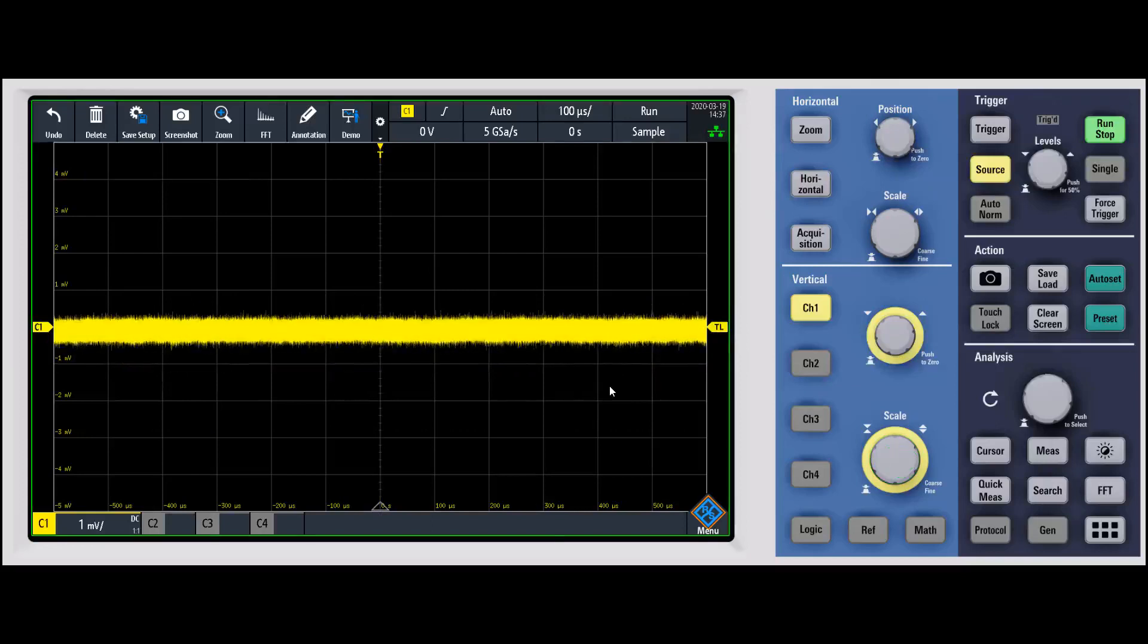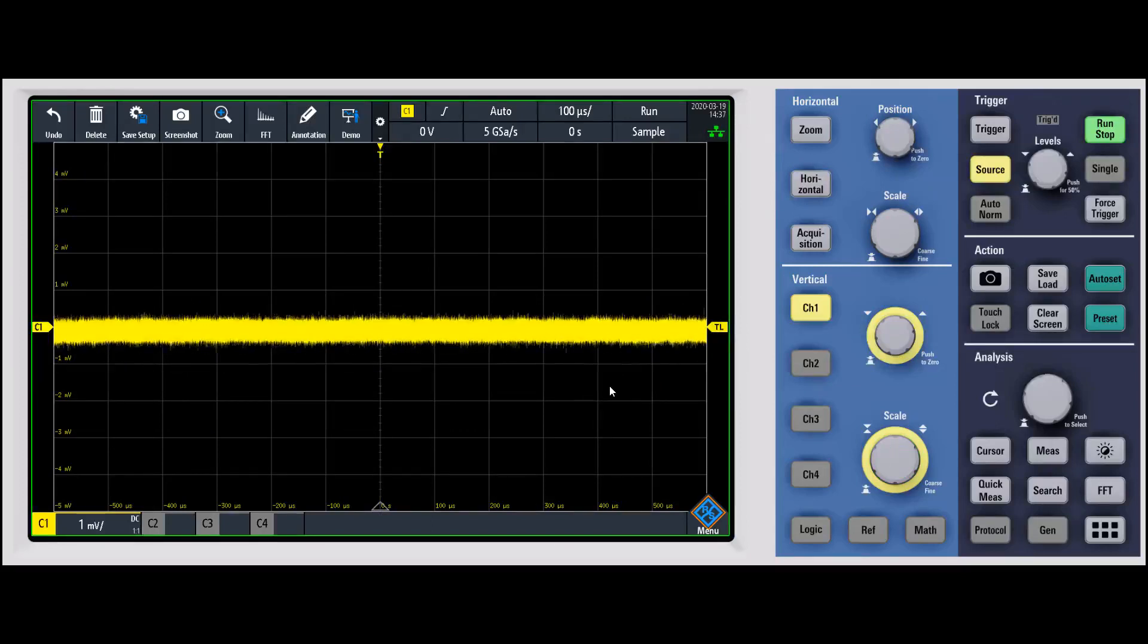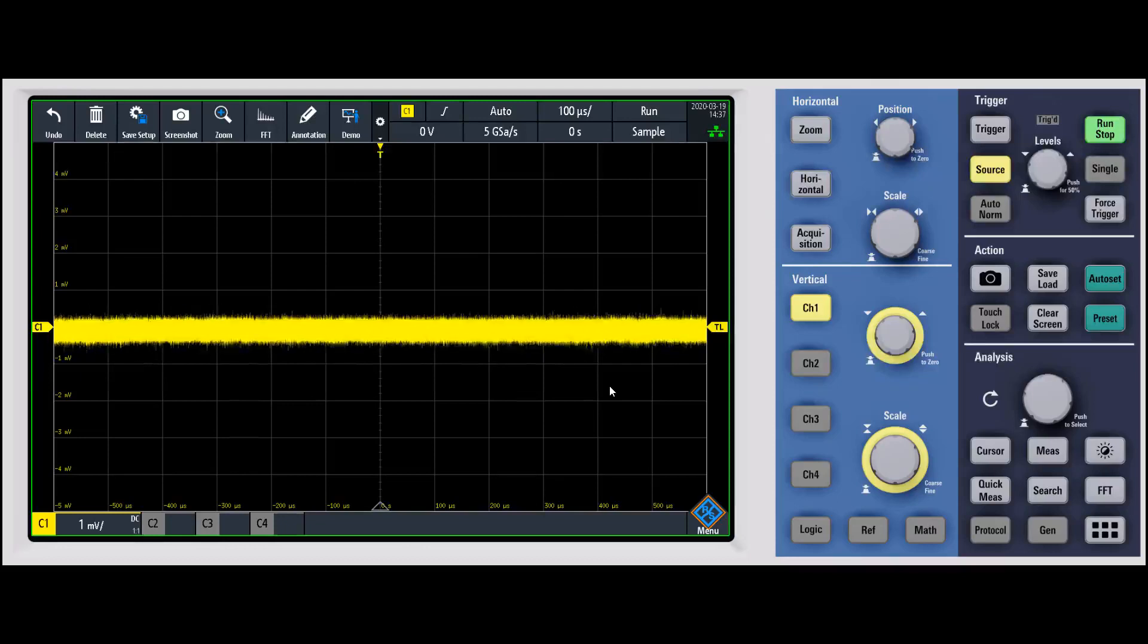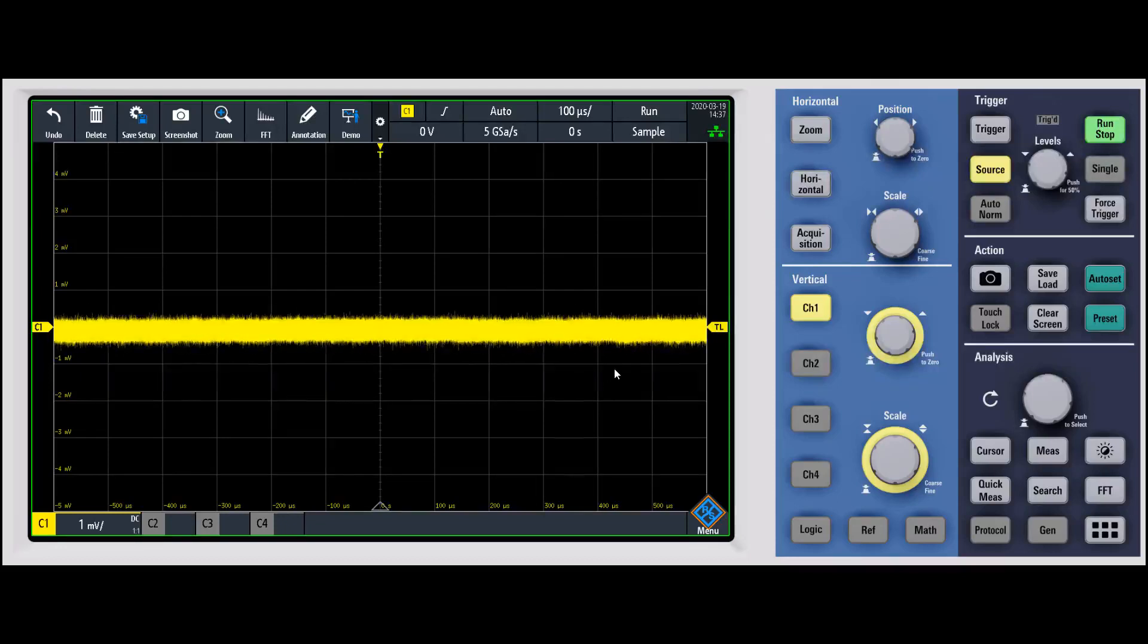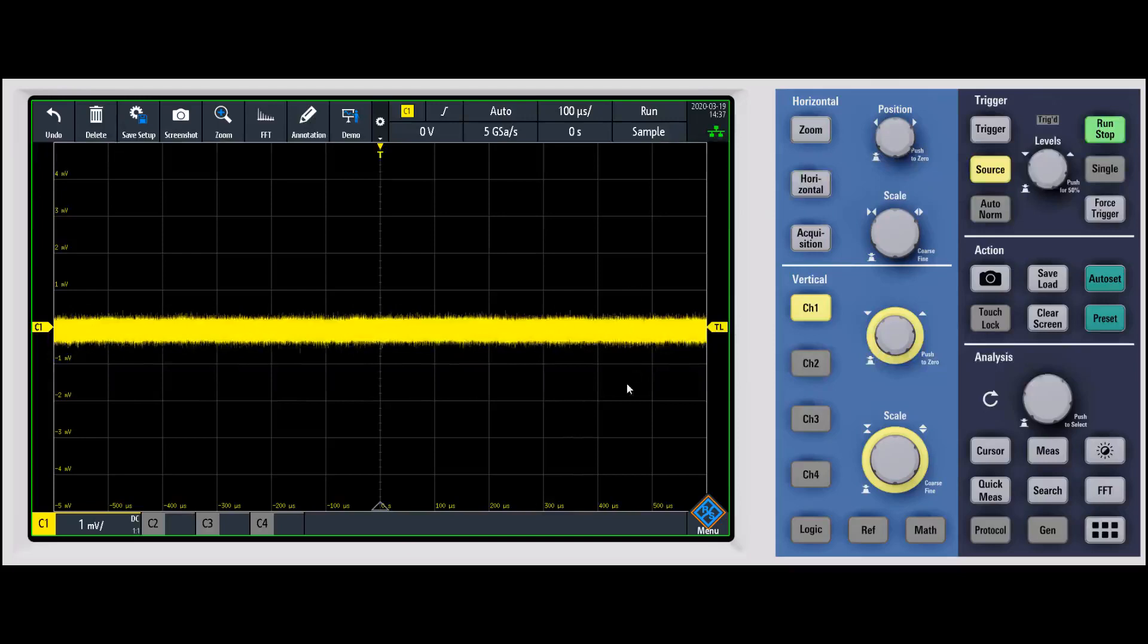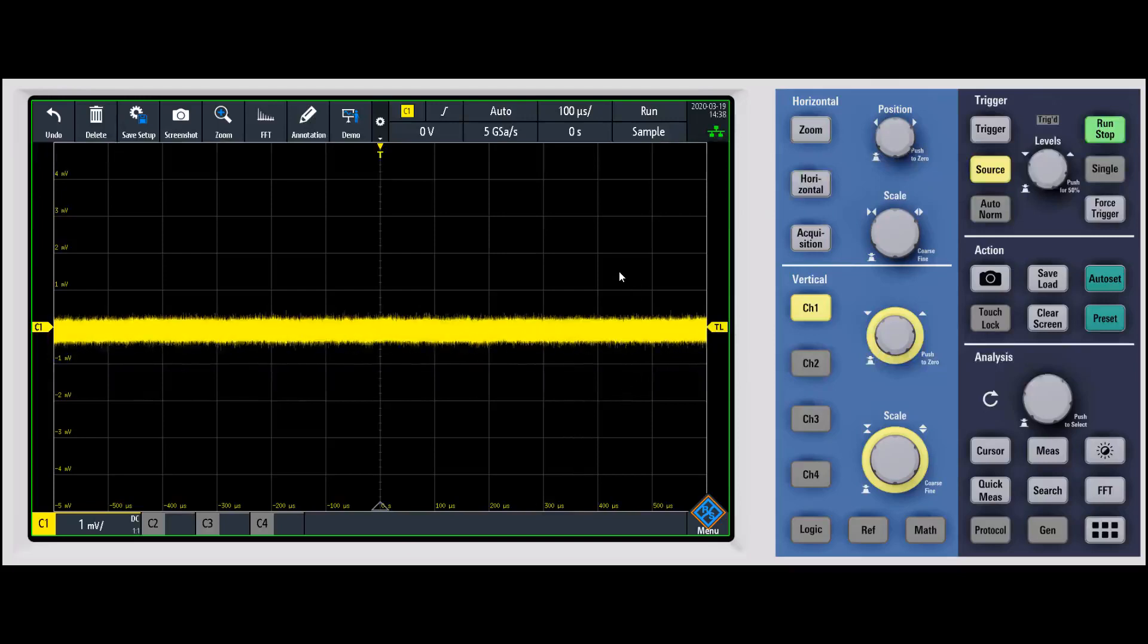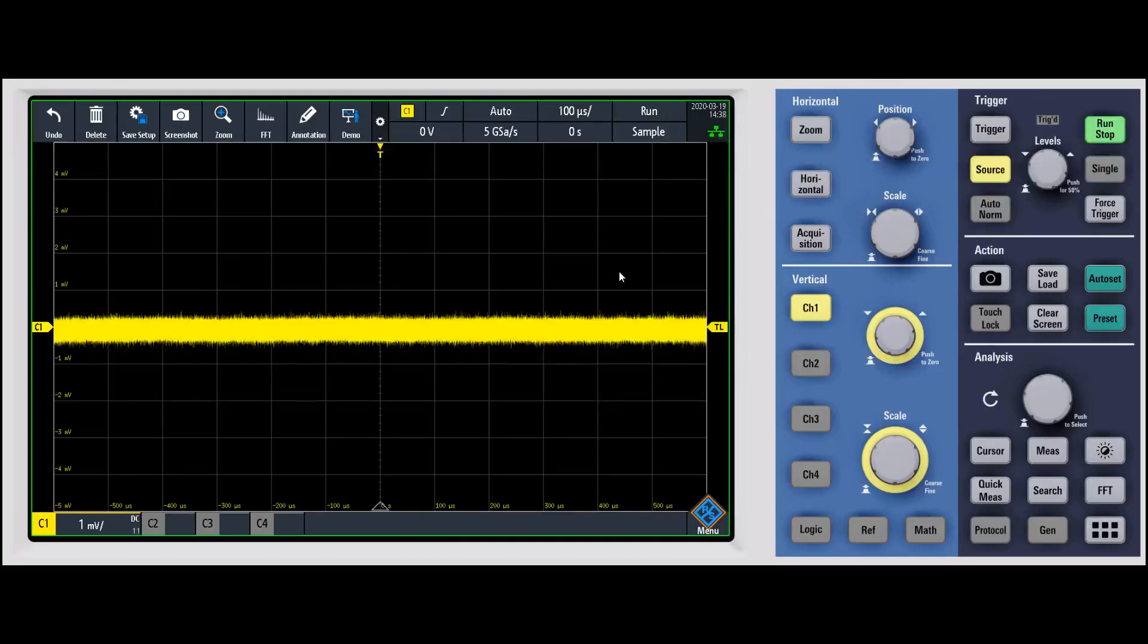One of the first things that you'll notice is the noise visually is actually pretty small. As you go to these smaller volt per division settings, one of the things you might notice on other scopes is they'll take up several divisions worth of display with the actual analog noise of the oscilloscope.